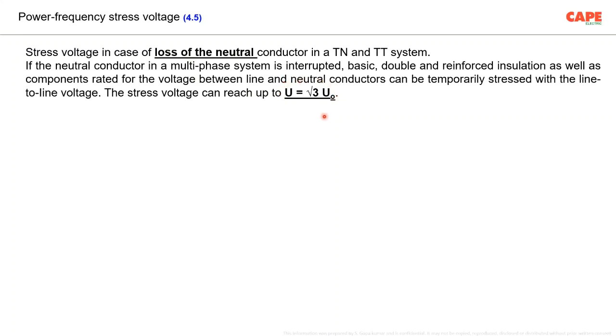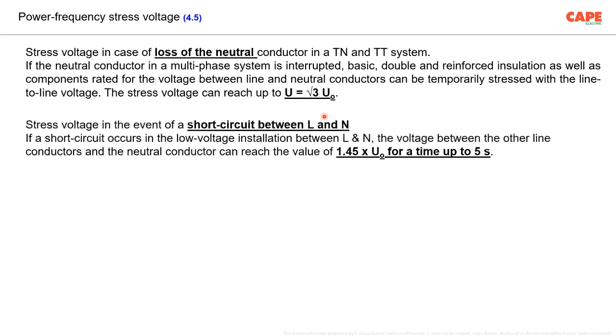The phase-to-phase voltage will be applicable under this condition in your single phase electrical equipment, depending upon what equipment you switched on, depending upon what kind of equipment are connected to the other phases. Basically, two phases will experience this much voltage to the respective neutral. And if this voltage is not disconnected before a certain time, of course, your equipment is supposed to fail.